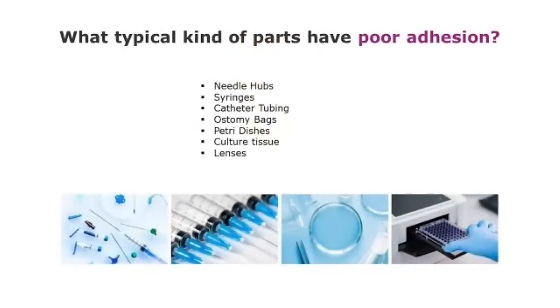So some of the typical parts that we run across in the medical device industry that are looking for some sort of corona or plasma surface treatment: needle hubs. Simply gluing the cannula into the opening of the needle hub is a very, very challenging process without improving the wettability and the adhesion properties of a polypropylene hub. So what we typically do is we will shoot a high voltage electrode into the opening, or even use an atmospheric plasma into the opening of the hub to create wettability and adhesion improvement, so that when the cannula is inserted and the glue is put in place, it gets good wetting and good adhesion improvement.